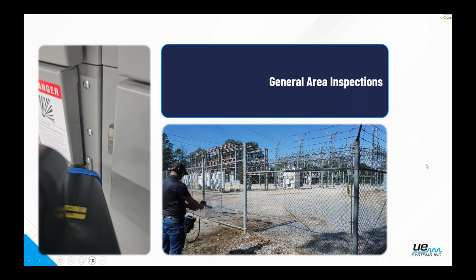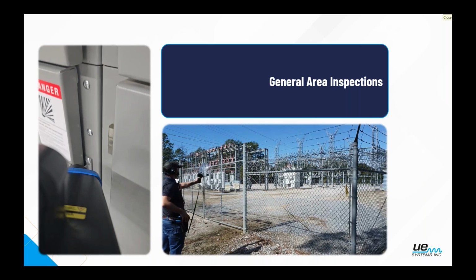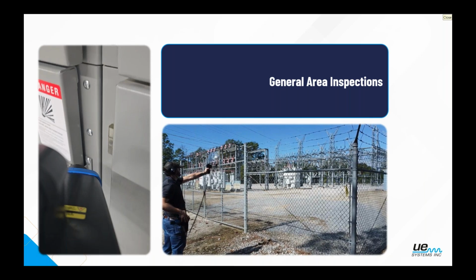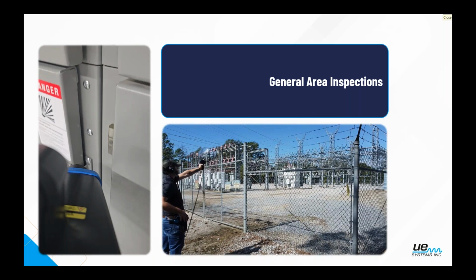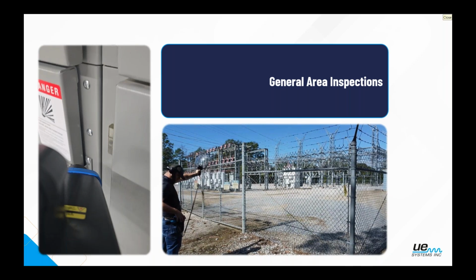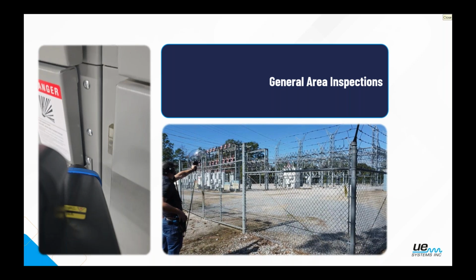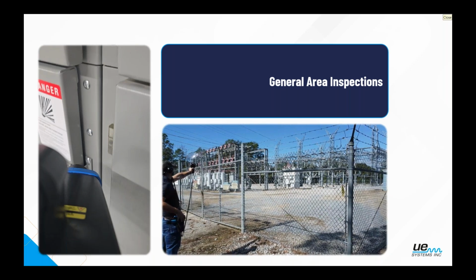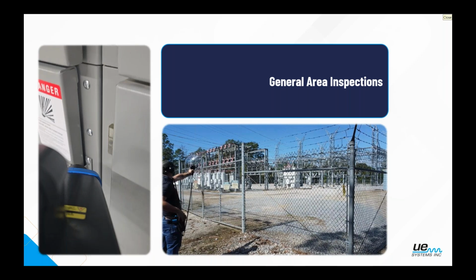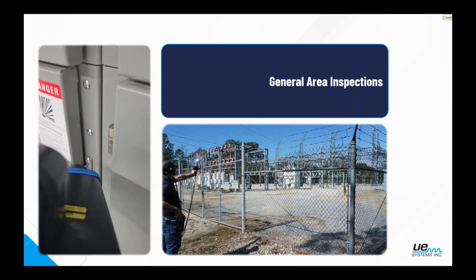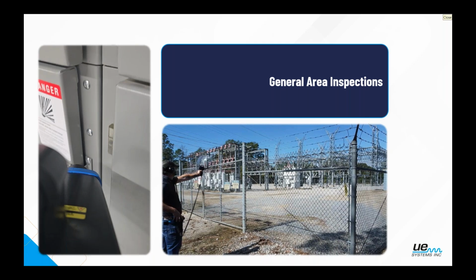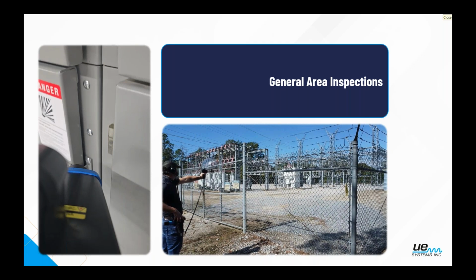But biggest thing is, just like with any other inspection, make sure we're on 40 kilohertz and the sensitivity dialed in to where we actually can hear clearly. And instead of doing that broad sweeping, we're actually able to pinpoint each individual component. So here I'm looking at connections, the bushing of the transformer, anywhere where there could be something like tracking, arcing, or corona happening. And just able to slowly sweep.